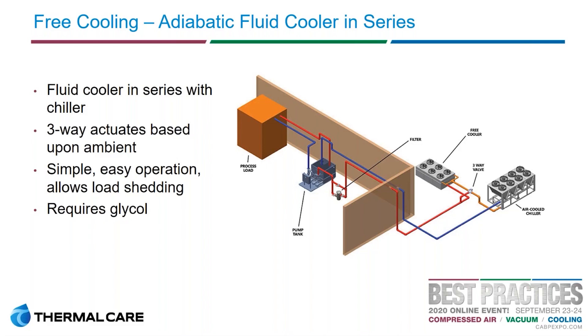We have that fluid cooler — which in this case could be a traditional dry one or the adiabatic style — and we put it in series with the air-cooled chiller. In the coldest months of the year, we can send the hot water returning from the process through this fluid cooler, or free cooler, before it goes to the chiller. This removes heat from the system before the chiller even sees it, allowing the chiller to either turn off completely or consume less energy — which is part of load shedding, which we'll cover shortly.